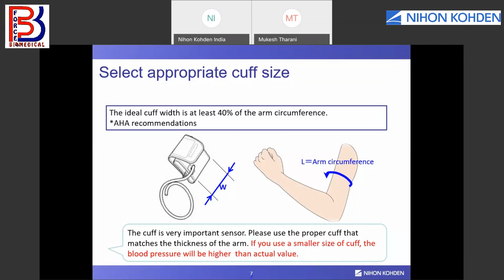As we can see in the previous slides, there are various sizes of the cuff available. The cuff is a very important sensor. Please use the proper cuff that matches the thickness of the arm. If you use a smaller cuff, the blood pressure will be higher than the actual one. So we need to be careful while selecting the NIBP cuff on the patient.